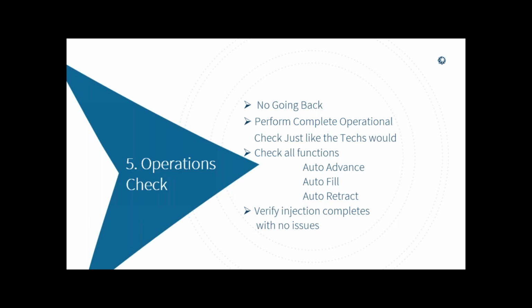Operations check. Once you get started, there's no going back. So you run an operations check on any injector. You run a simple operations check with your syringes. You do everything like the customer would do. In the Bayer manual for the Stellant, it actually has a protocol in there, and it tells you what to run.